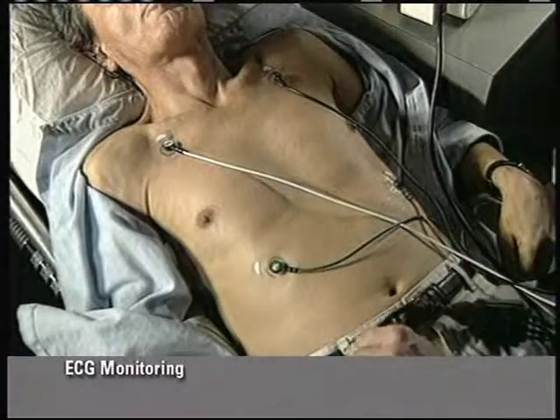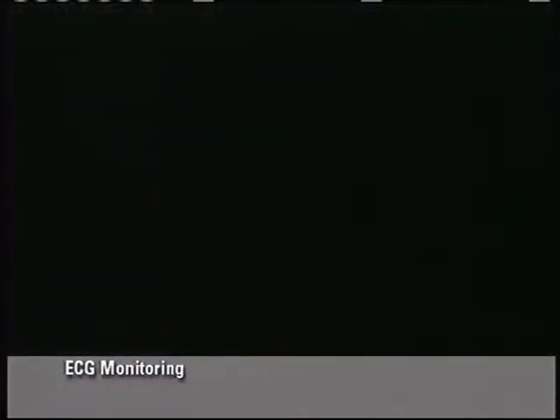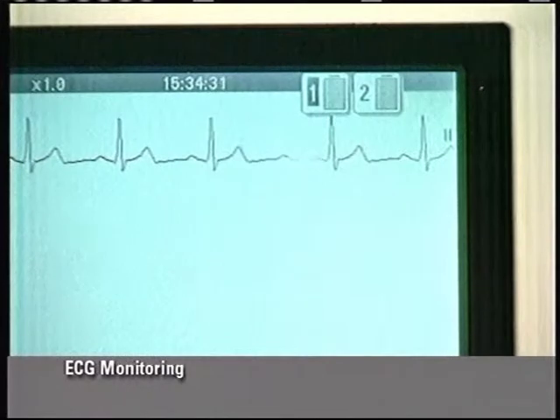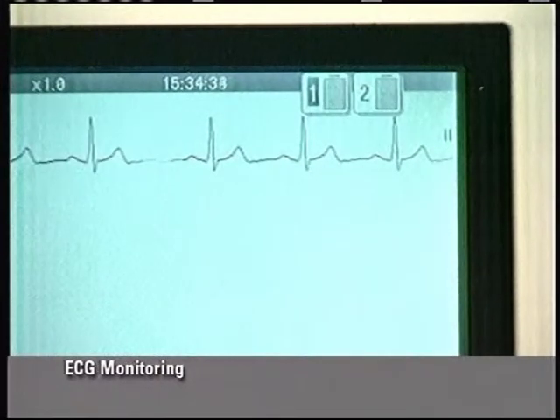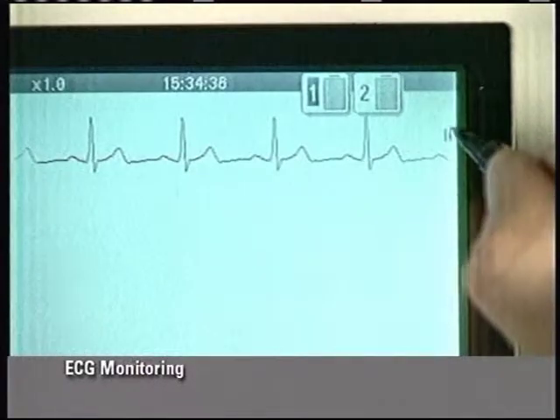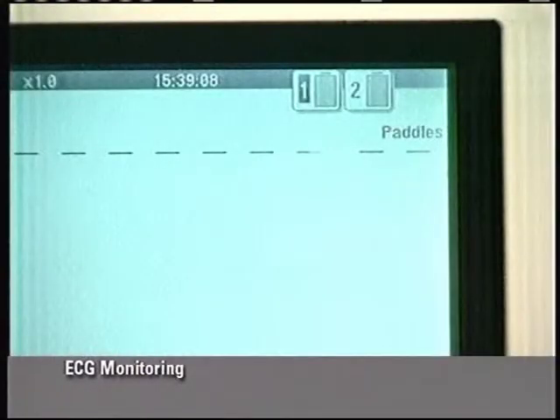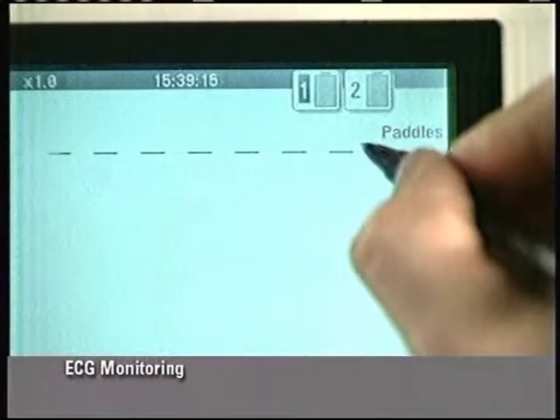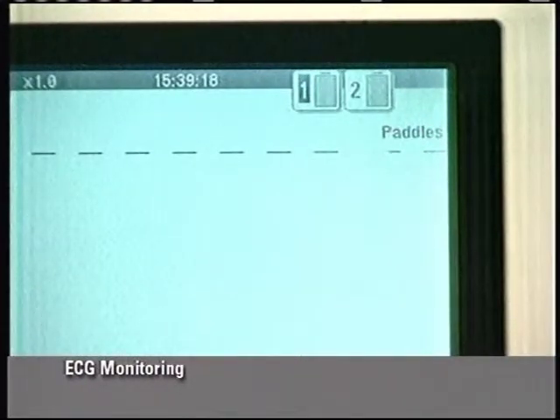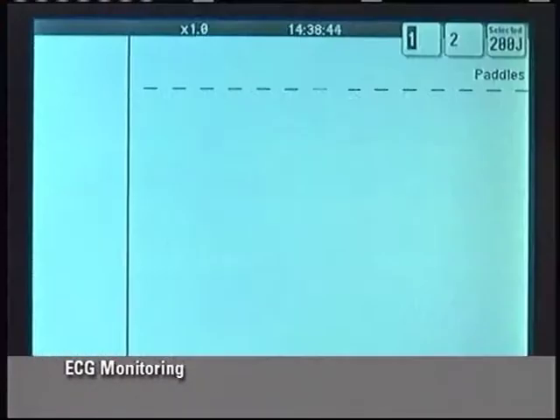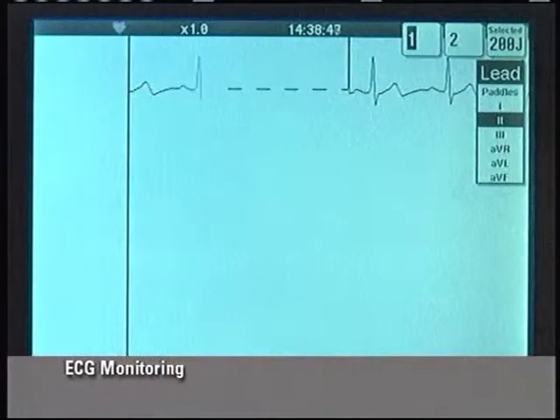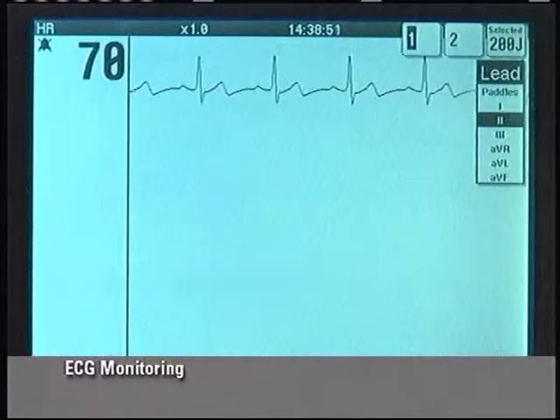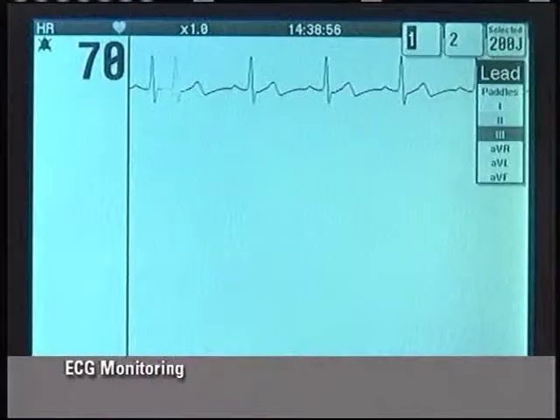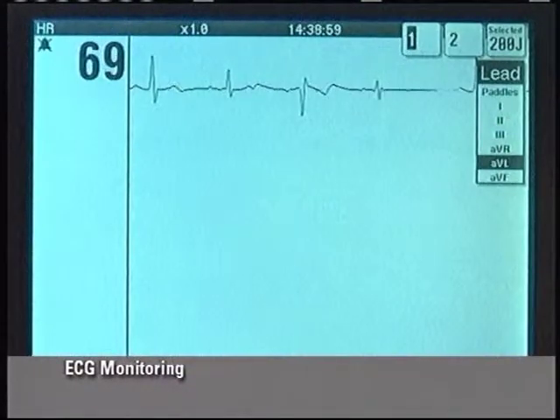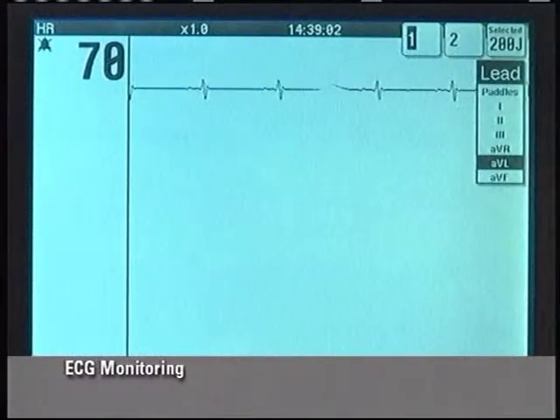Secure the cable with the clasp to prevent tension on the electrodes. Check that the ECG is displayed on the screen. If the power on default is lead 2, the patient's ECG and the indicator 2 are displayed. If the power on default for the ECG is paddles lead, the screen displays a dashed line and the lead indicated is paddles. To change to lead 2 or any other lead, press the lead button. The ECG lead menu appears and the lead automatically changes to lead 2. If another lead is desired, continue to press the lead button or rotate the selector. After a few seconds, the menu disappears, or you can press the home screen button.